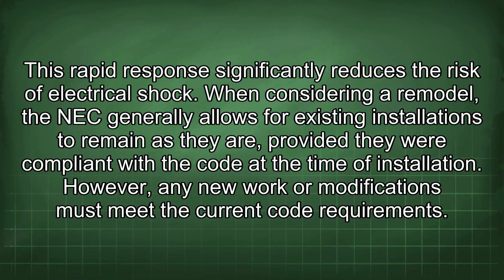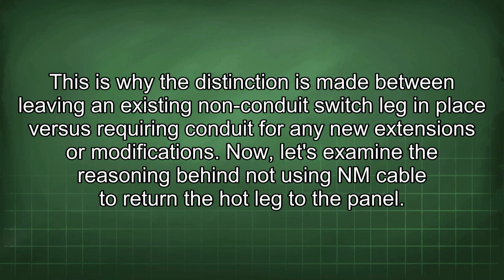When considering a remodel, the NEC generally allows for existing installations to remain as they are, provided they were compliant with the code at the time of installation. However, any new work or modifications must meet the current code requirements. This is why the distinction is made between leaving an existing non-conduit switch leg in place versus requiring conduit for any new extensions or modifications.